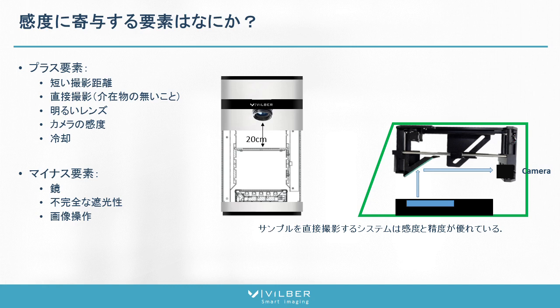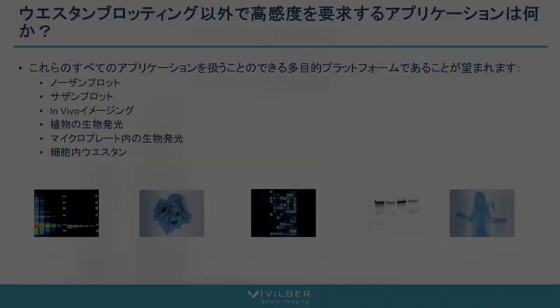The last factor, which is totally determining for Western blot images, is the cooling of the camera. You need exposure times in order to take your image, and exposure times mean you collect light for some time. Unfortunately, you also collect thermal energy from the atmosphere, which creates noise in your image. In order to avoid collecting this energy, you need to cool the camera. With very important cooling, your camera can have very long exposure times, like a few minutes. If the cooling is inconsistent and too low, unfortunately the exposure times will not extend very far — just a few seconds.